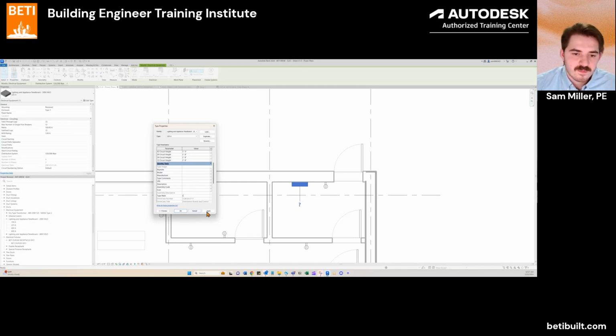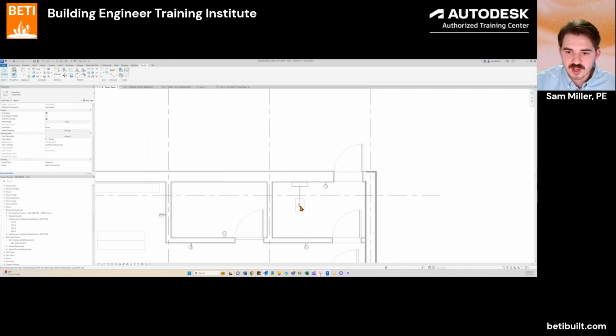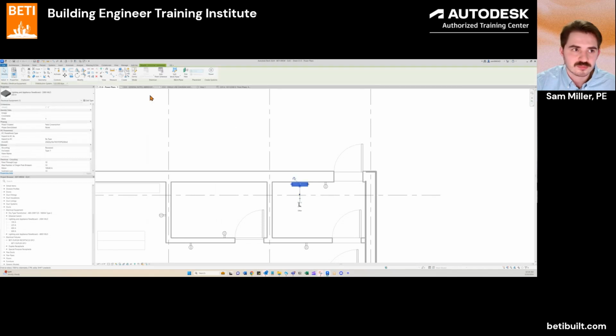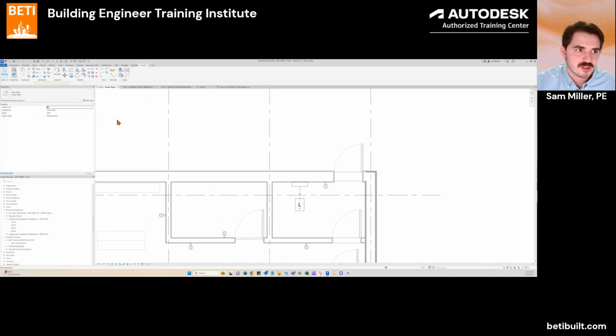L. In a building where I'm using 480 and 208, I like to name the 480 volt panels with H's, maybe like H1, H2 if I'm using multiple, and then the low voltage panels or 208 panels as L, L1, L2. You can really name it anything you want. This is just a best practice thing. And so now you'll see that my tag comes up. If I want to get rid of this leader, I can click here and make it look a little bit nicer.